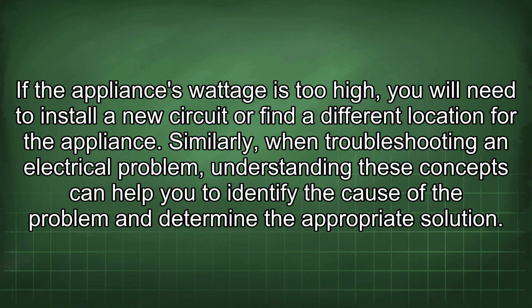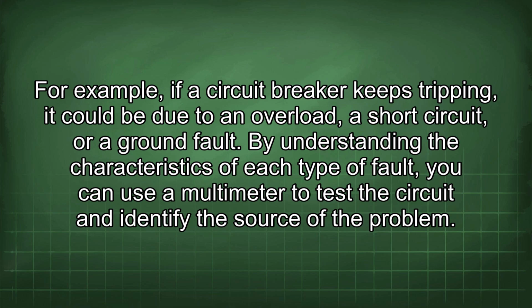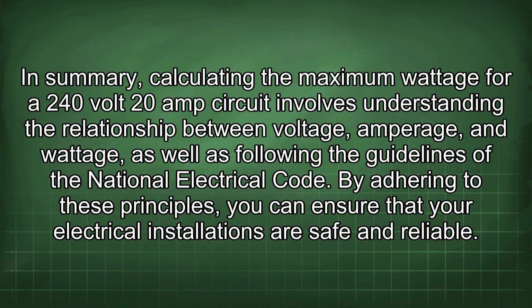Similarly, when troubleshooting an electrical problem, understanding these concepts can help you to identify the cause of the problem and determine the appropriate solution. For example, if a circuit breaker keeps tripping, it could be due to an overload, a short circuit, or a ground fault. By understanding the characteristics of each type of fault, you can use a multimeter to test the circuit and identify the source of the problem. In summary, calculating the maximum wattage for a 240 volt 20 amp circuit involves understanding the relationship between voltage, amperage, and wattage, as well as following the guidelines of the National Electrical Code. By adhering to these principles, you can ensure that your electrical installations are safe and reliable.